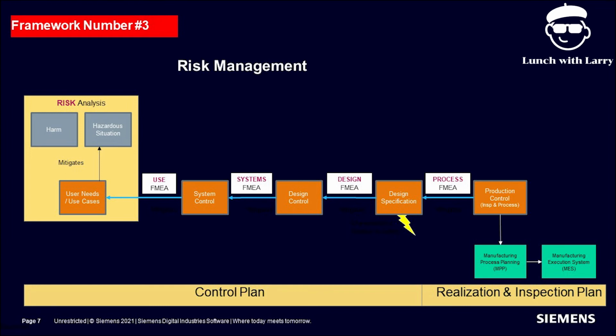What's really important now is that we have a total design control plan where we've identified each level of control and the progression needed to get to the level where the actual characteristics of the design are defined. And if the traceability shows that those characteristics lead directly to a hazardous situation harm combination that is of high risk, then we understand that those design specifications are critical to quality characteristics and should be processed through a process failure mode analysis to get the set of production controls to assure that we have control of the production process as well. So we'd have our inspections and our process controls, like heater band temperatures or measurements of the product, to assure that the design specifications have been met.